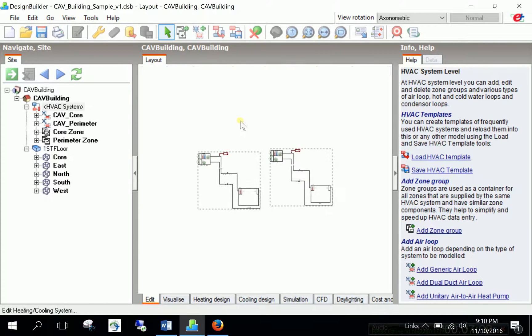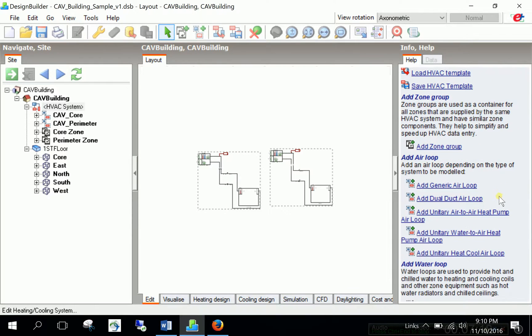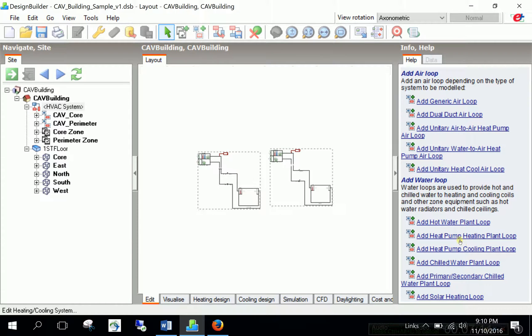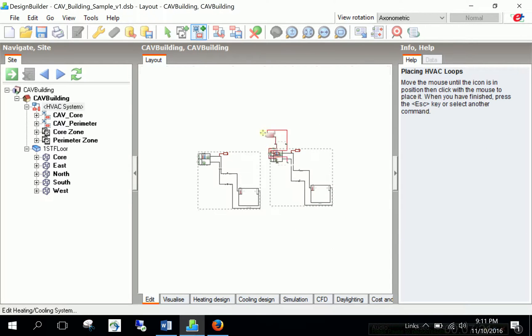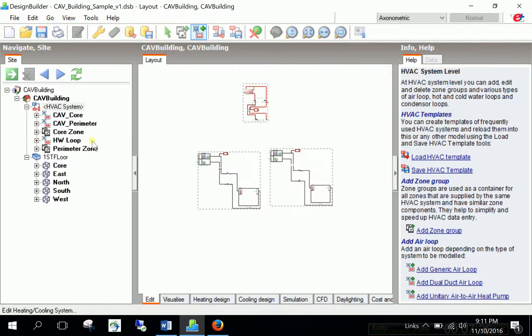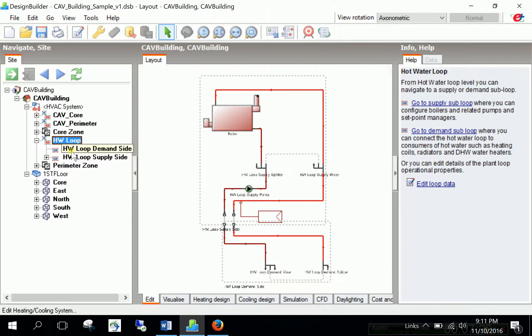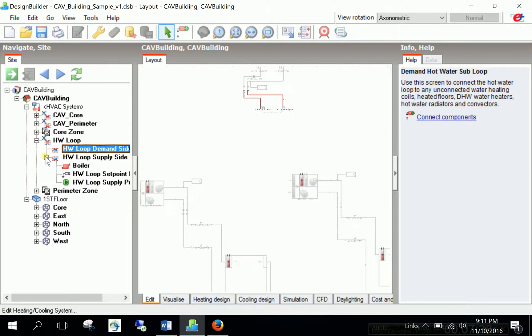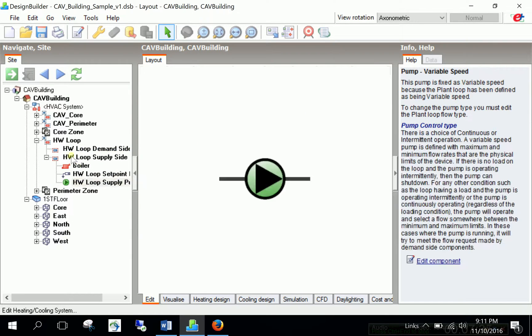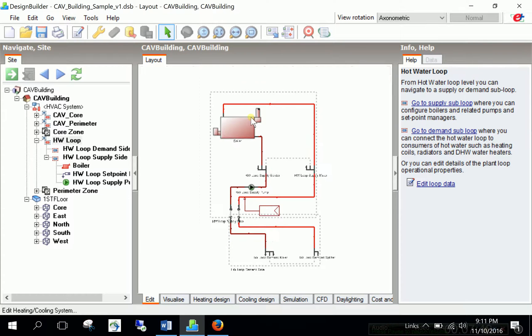How about the plant side? Now, we finished the loops and the connections on the air side. But on the plant side. Like the water side systems. Basically. What are we going to add? So, it's similar. Just scroll down. And you should stay at that level. HVAC system level. And add hot water plant loop. So, say okay. I will add this plant loop somewhere here. Again, I have hot water loop. And the hot water loop has a demand side. Which is ready for connectivity. And I have the boiler on the supply side. A set point manager. And a pump. Basically the same thing. So, is there a difference between CAV and VAV in terms of hot water loop and the boiler? No. They are totally the same. No change. The same thing here.